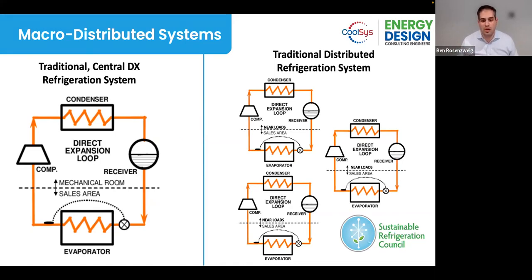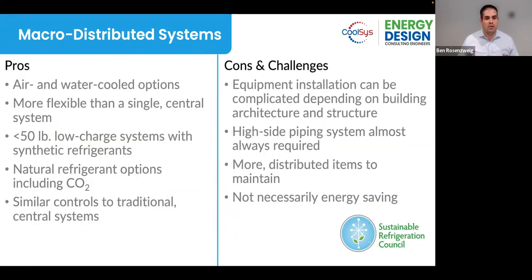This has been a popular system architecture that many retailers have used for decades in the United States and continues to be with low GWP refrigerants. Next slide, please. So some of the quick pros and cons about macro distributed systems are there's air and water cooled options. They're very flexible. Lower than 50-pound charge systems qualify as low charge systems in many places. You can use CO2, and they have similar controls to traditional central refrigeration systems, which could be easy in terms of installation and maintenance on that side.